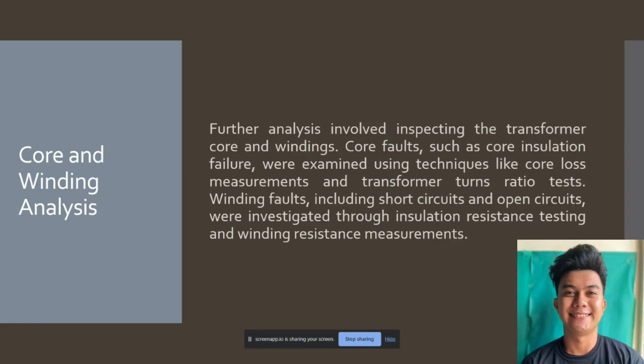Core and windings analysis. Further analysis involved inspecting the transformer core and windings. Core faults such as core insulation failure were examined using techniques like core loss measurements and transformer turn ratio tests. Winding faults include short circuits and open circuits, which were investigated through insulation resistance testing and winding resistance measurement.